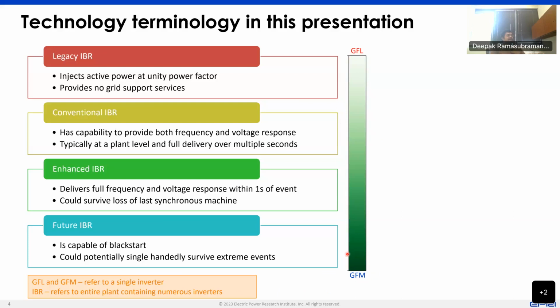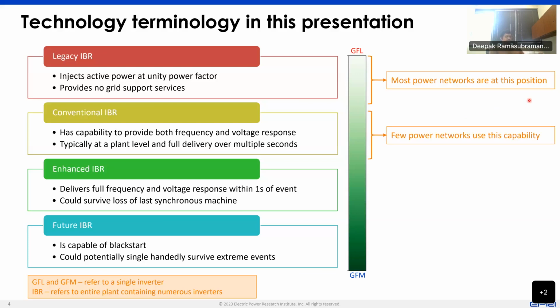And now, if we take this outline of the categories that we have and we lay upon it the way these categories are used in power networks around the world, most power networks, and here when I say power networks, I'm talking about large power systems, most of them are still at this position where the majority of the inverters are still legacy inverters. There are few networks that have started using this capability of the conventional IBR. They have started requiring it as a minimum requirement for interconnection, but the deliverability of that capability is not necessarily guaranteed. It could just be that the capability is there and enabled, but there's no guarantee that it's going to be delivered. But across these two sets is probably the majority of the power systems around the world.